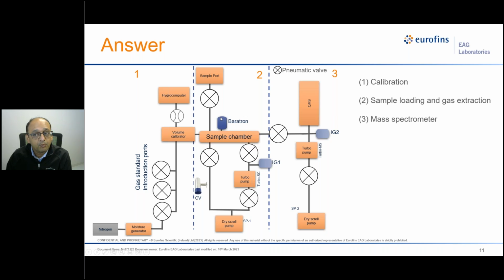And let's talk about the sample port. The sample port is where we attach the sample to a mechanism where we can puncture the sample. While loading the sample, we generally close this valve so that the rest of the system remains isolated and remains at the lower gas background. Once the sample is mounted, the sample port valve and the bypass valve, which is directly on the left side of the sample chamber here, are opened, and we attain the rough vacuum first. Once that is done, we move to the turbo pump system to get a better background. We will see a little more detail in a later slide.